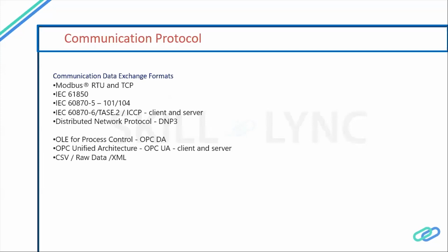These are the communication protocols: Modbus RTU and TCP, IEC 60870-5-101 and 104, client-server distributed network, DNP3, OPC UA and raw data XML. Modbus RTU is a very basic communication protocol, used in energy meters and protection relays. A lot of devices come with Modbus RTU. With RTU you can use a cable length of up to 1.2 kilometers, but the speed is very low, 19.2 kbps only. And Modbus TCP distance is not more than 100 meters in any case, and the speed is 100 Mbps.